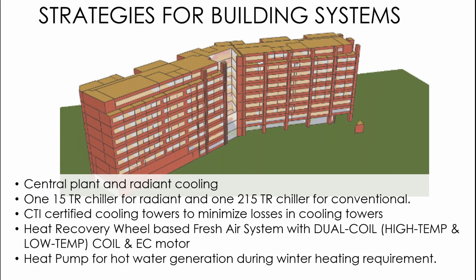Conventionally, people have been using electric boilers, which are also called hot water generators, which are extremely inefficient but cheaper. What we have proposed is a reverse cycle heat pump. We have an outdoor unit of a VRV or a split unit. What does an outdoor unit do? It throws out hot air. Now what if I use that hot air to generate hot water? This is what is called a heat pump. It basically works in a reverse cycle and gives me hot water. It is about 4 to 5 times more expensive than a hot water generator, but consumes almost 1/6 to 1/7 of the power.